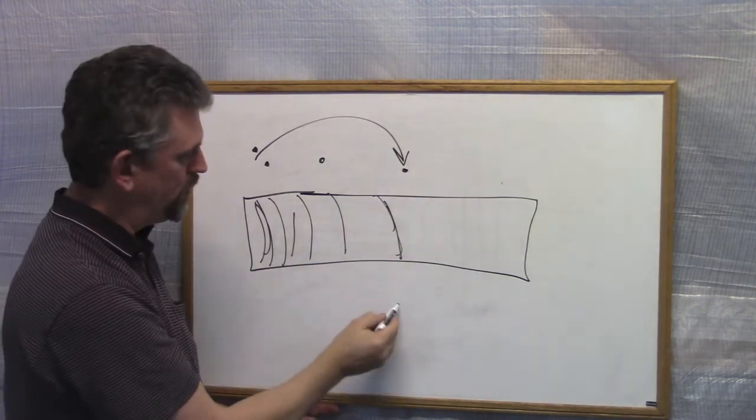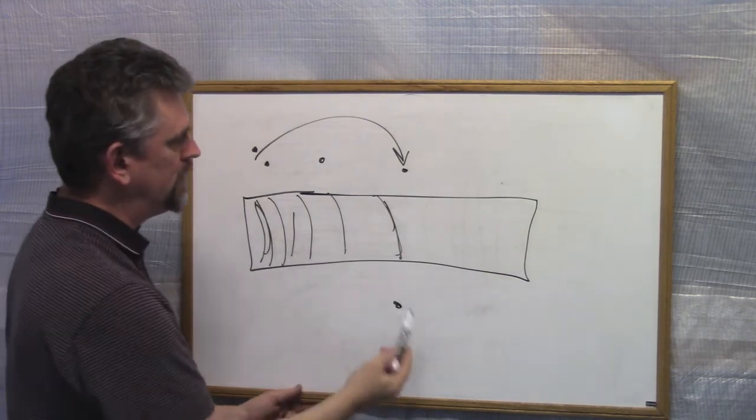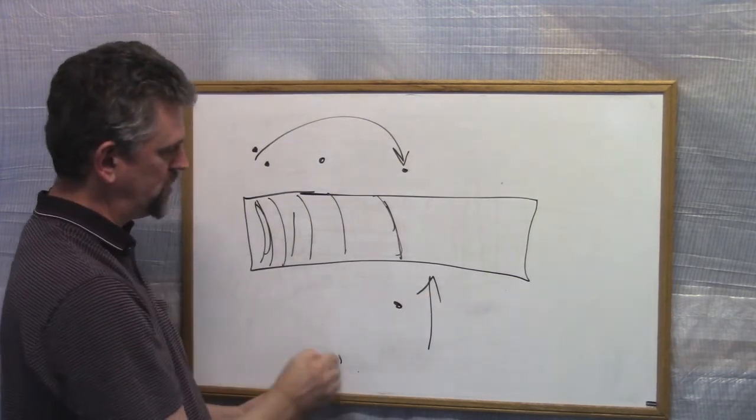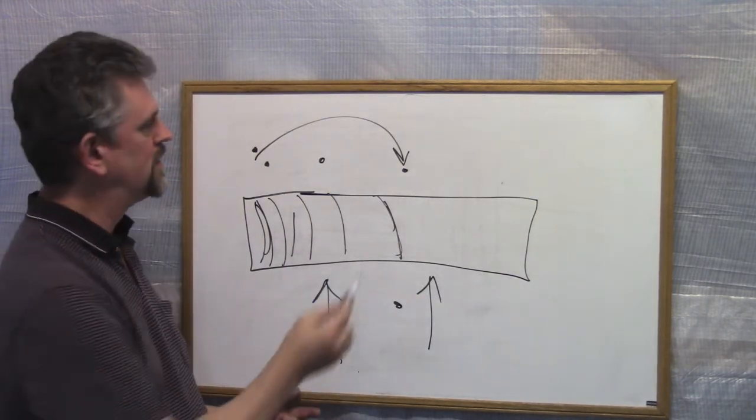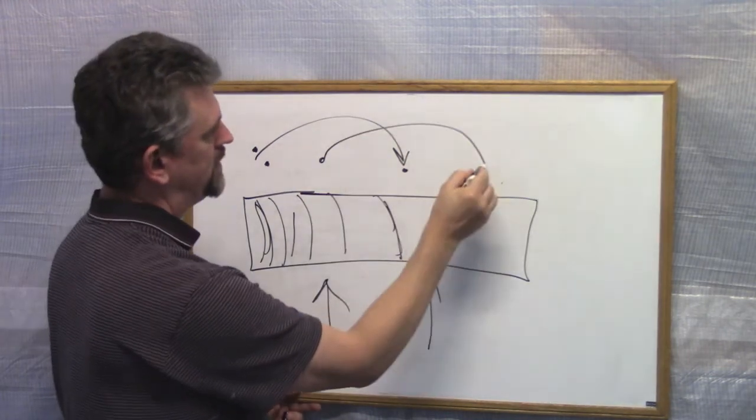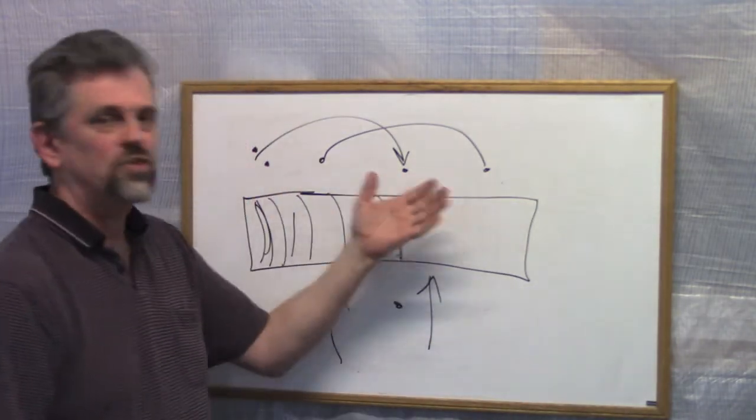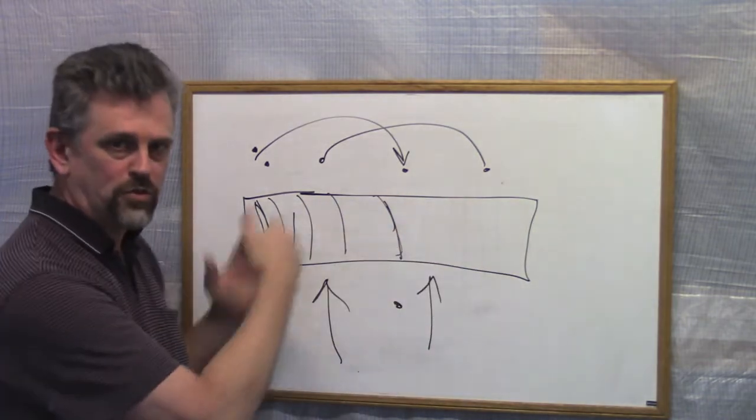When you get over here, you move these instruments. And then, the whole time, maybe you have a reference instrument over here. This is, of course, assuming the current always is that direction. And then, you move that instrument over there. So that way, you don't need that many instruments. You don't need to have, even if you have 30 stations, let's say, you don't need to have 30 instruments because you keep moving them.